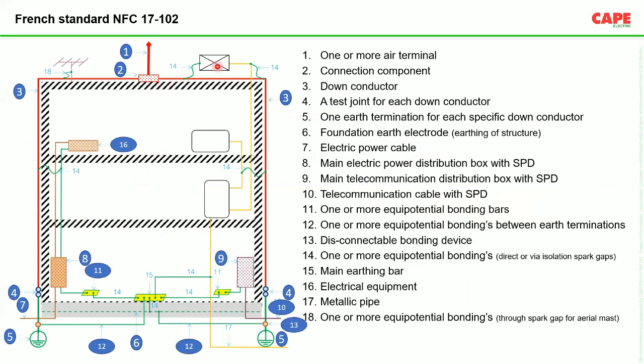The French standard is explaining the system in detail. You need to have several safety measures in a building. Over and above, you see this item number 1. This is the ESE rod. So basically, you need to have serial number 1 to 18. If you go as per the Indian standard IS/IEC 62305, you can achieve safety by using items serial number 2 to 18. Item number 1 is absolutely not required.